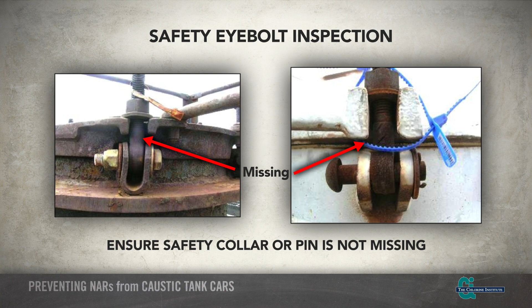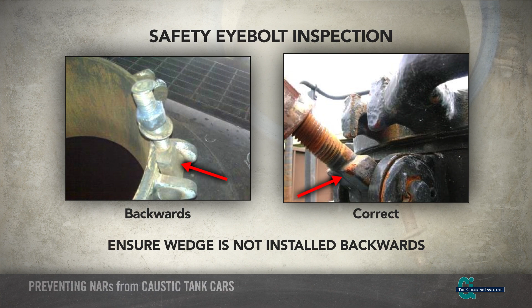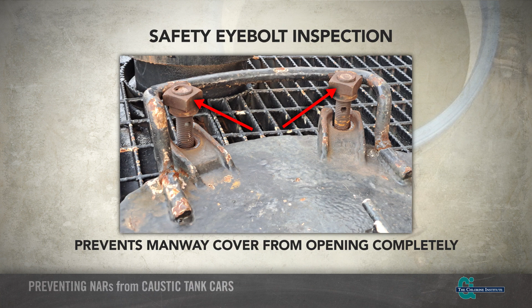For collar and pin style safety eye bolts, verify the collar or pin is not missing. For safety eye bolts designed with a wedged bottom, it is important to ensure that there is no damage and that the eye bolt is not installed backwards. The correct position for the wedge-style eye bolt is for the sloped edge of the wedge to face the manway when in the upright position. For interference-style safety eye bolts, it is important to verify that the eye bolts do prevent the manway cover from opening all the way before fully untightening the bolts.